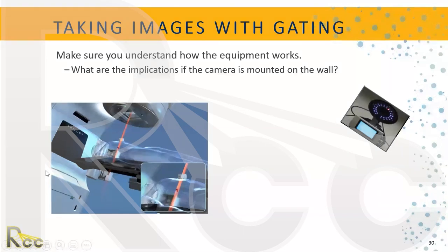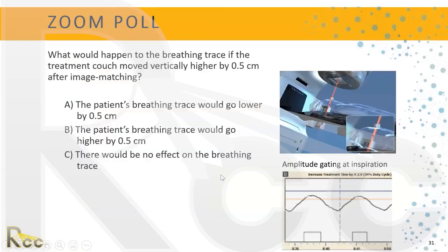An important consideration about the equipment: the camera is mounted on the wall in a stationary position. We set the patient up based on their tattoos and position on the table. So what happens to the breathing trace if the treatment couch is moved vertically higher by half a centimeter after image matching?